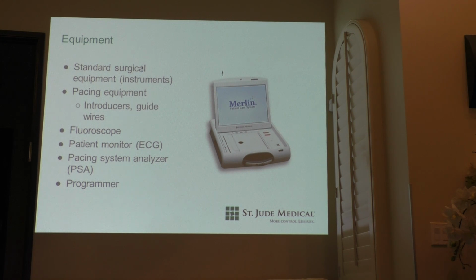We use a programmer. This is different on every brand. So they're all proprietary, and they're required in order to interface with a different branded device. St. Jude's is white, Medtronic's is blue, Boston's is greenish, kind of. Biotronik is white, and Sorin's is not very good. So most of them have touch screens. Everything's basically included in the box, and they include the ability to connect a patient EKG directly to it, which is really good if you ever get asked to check one. Always look at the EKG because it's a good way to make sure that you're still pacing.